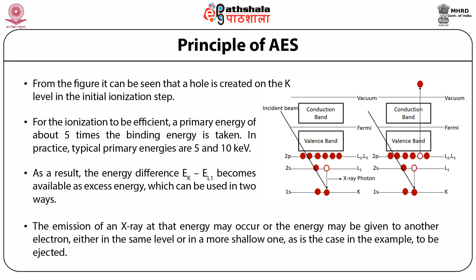A clear transition from electron to photon emission is evident in this chart for increasing atomic number. For heavier elements, X-ray yield becomes greater than Auger yield, indicating an increased difficulty in measuring the Auger peaks for large Z values. Conversely, Auger electron spectroscopy is sensitive to the lighter elements, and unlike X-ray fluorescence, Auger peaks can be detected from elements as light as lithium, Z equal to 3.